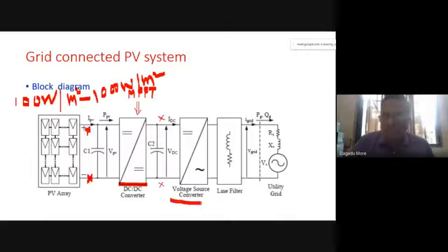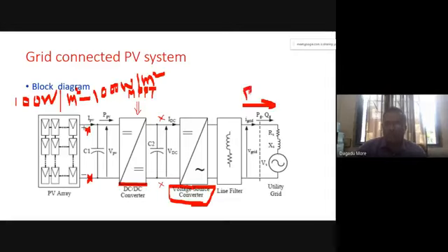Here we have seen a voltage source converter, or you can call it a PWM inverter and PWM rectifier. We already studied this. These are PWM converters, and it is possible to supply both powers. Our active power will flow from the solar panel to the grid, but reactive power can flow in both directions, the Q power. We can supply the reactive power or we can absorb the reactive power. That is the beauty of our voltage source converters. So this system can give active power to the grid, it can supply reactive power, and it can absorb reactive power of the grid depending upon the requirement. This is what we call a grid connected PV system.